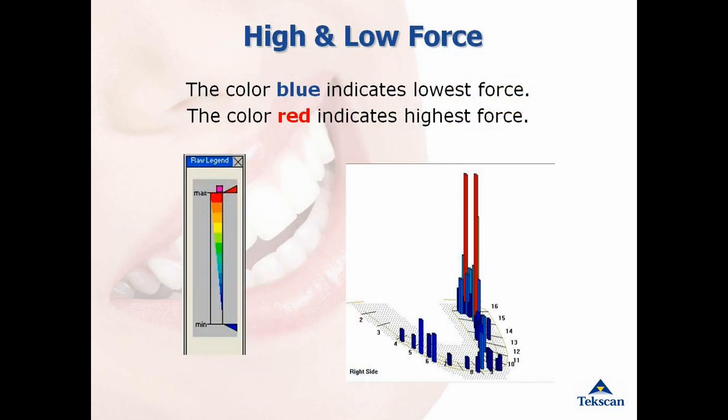The T-Scan system measures relative force. The software provides a force legend that shows the different force levels that can be graphically displayed by color coding — from lowest forces in blue, through middle forces in green and yellow, up to the highest forces in red and orange. The force legend illustrates the color coding which describes 256 levels of force that can be recorded in a given movie.